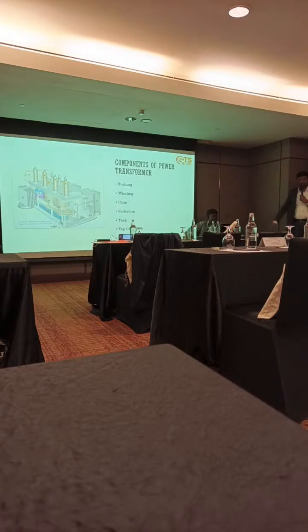Let's look into the transformer components. These are the major transformer components. There are bushings that are used to connect the cables, the HV and LV connectors, and the windings. In some cases it will be a two-winding transformer, in a few a three-winding transformer. That depends. Then we have the cores, where the windings are mounted. Then the radiators, the whole tank, and the tap changer, which is used to change the taps on the windings and the insulations.